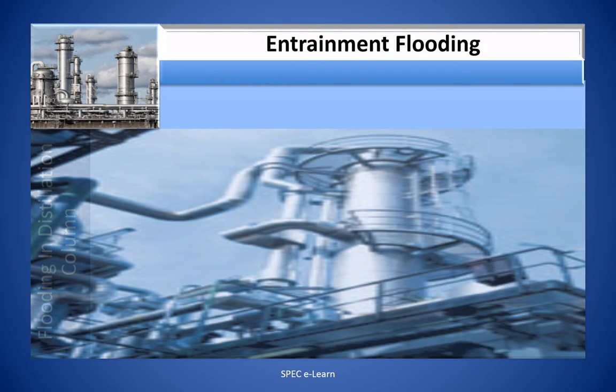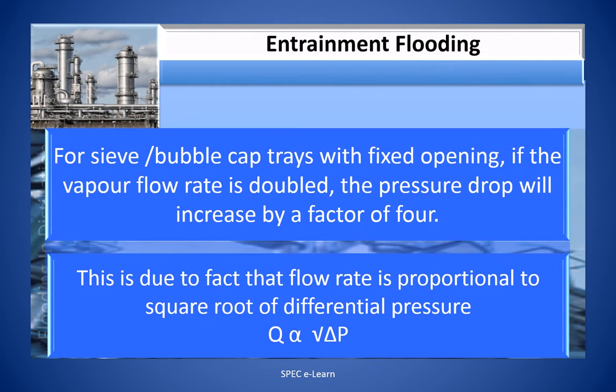For sieve and bubble trays with fixed openings, if the vapor flow rate is doubled, the pressure drop will increase by a factor of 4. This is due to the fact that flow rate is proportional to the square root of differential pressure.